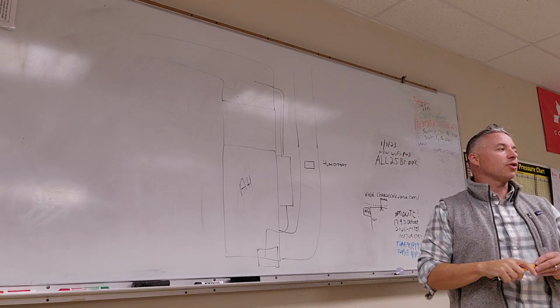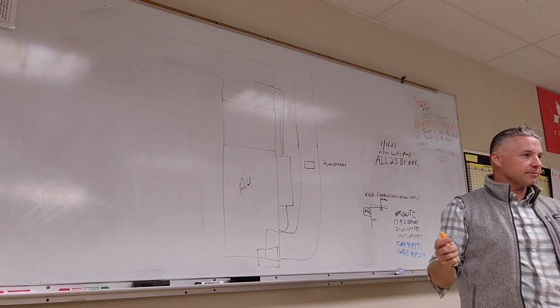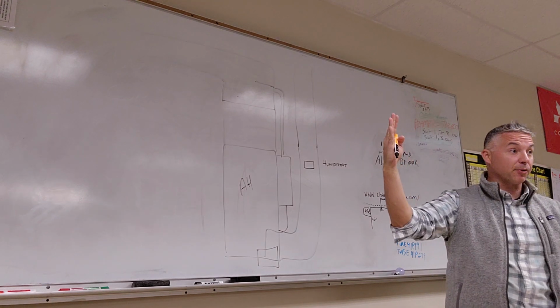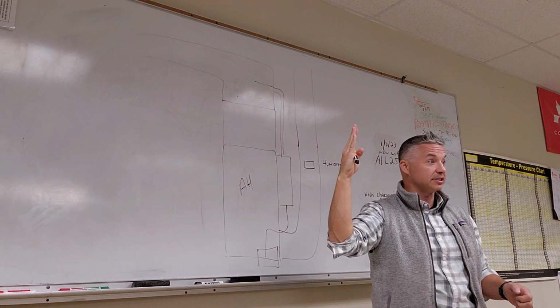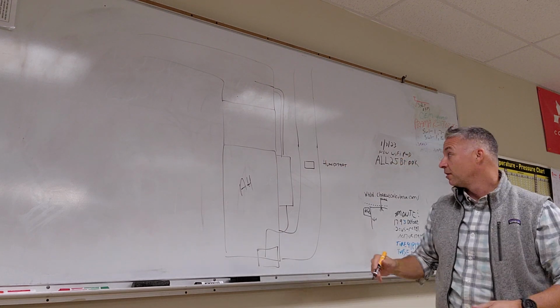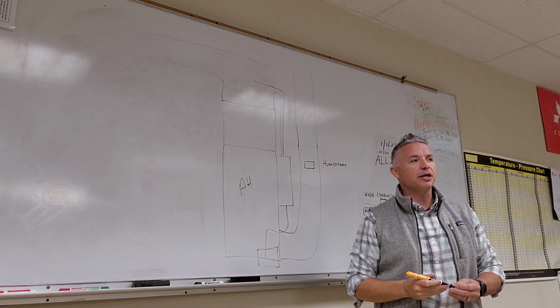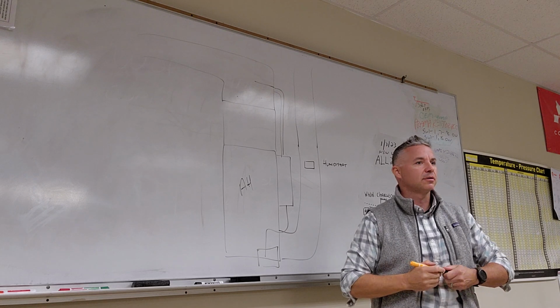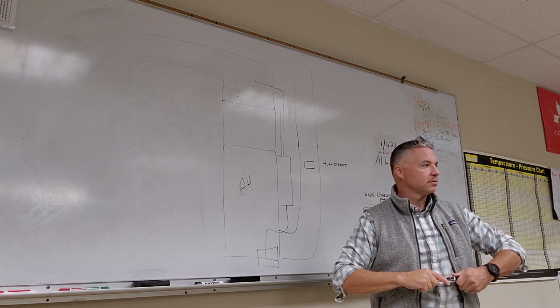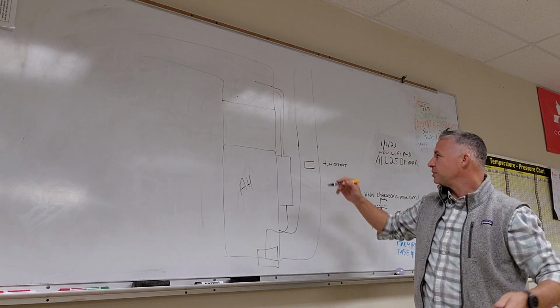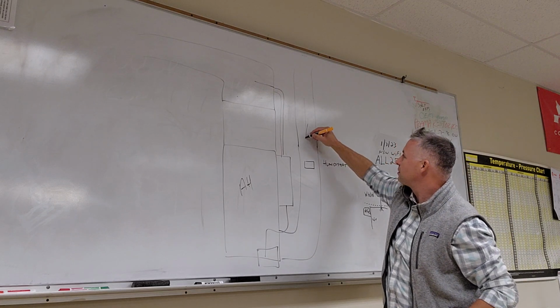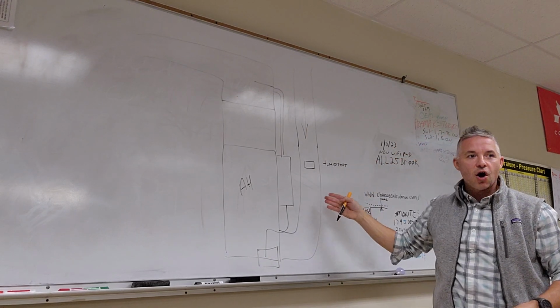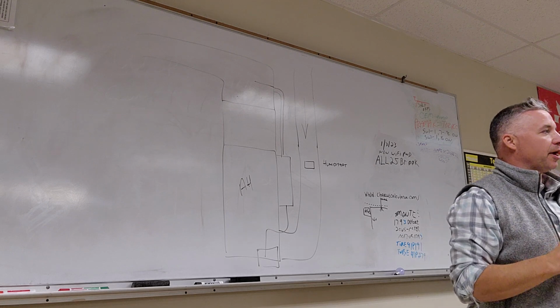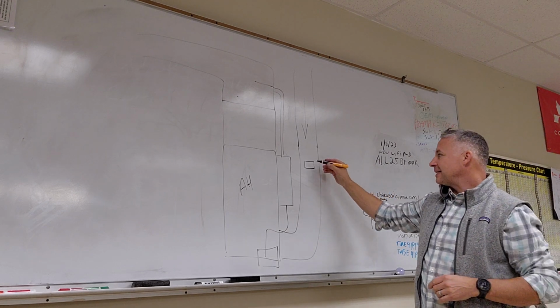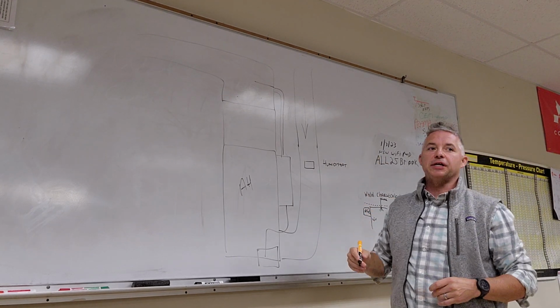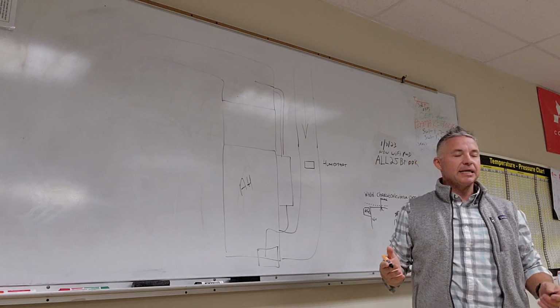The reason I call it a low limit or an operating limit is because it limits the operation, number one, right? It reaches a certain sensing level and it turns the humidifier off. We put them in the return ductwork. Why do you think we would mount it in the return ductwork? Good air coming back from upstairs. So it senses the return air that's coming back from the space, and it's reading the RH, the relative humidity in that return air. So that's telling this humidistat that it's currently 25% humidity in the space.